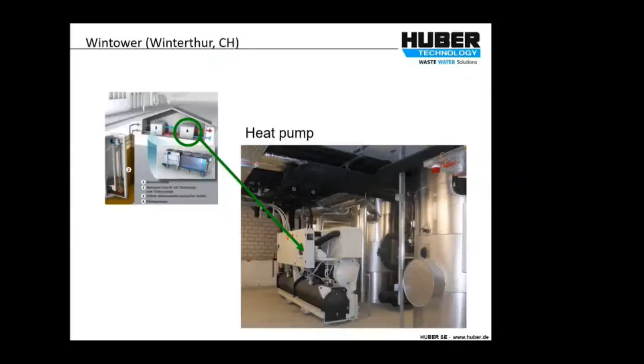So Winterthur in Switzerland, that was heating this building that you can see there, and on the right here is the screen that's just being dropped into the excavation that was made for the pump station there. So in this particular instance at Winterthur, the sewer flow was 60 litres a second, and the flow through our heat exchange units was about 60 litres a second. The thermal power generated was 600 kilowatts, but most importantly, the cooling effect was 480 kilowatts. So you tend to need cooling to make these projects economically viable.